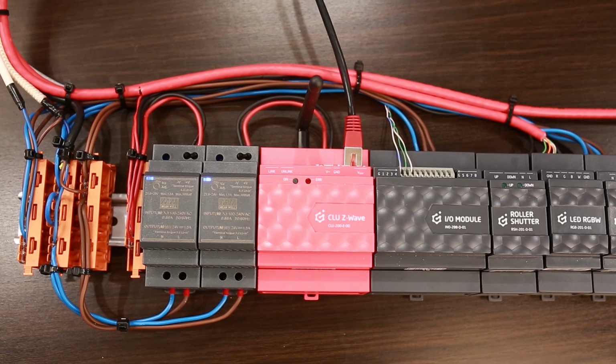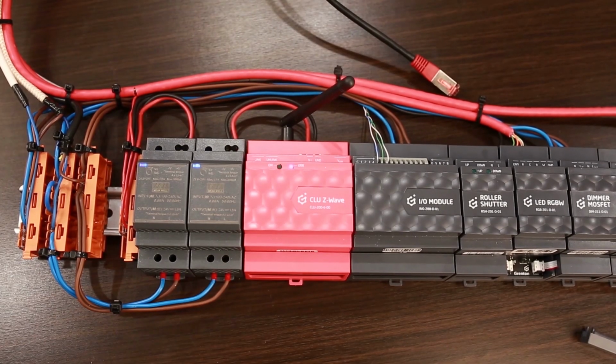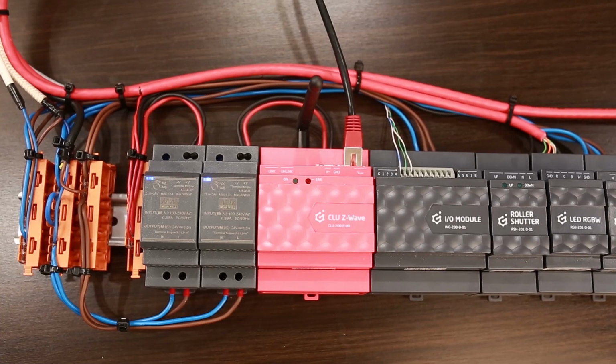This state that was seen earlier, i.e. alternately flashing red and green diode, means the so-called emergency mode, which is typical for a new CLU as it has no configuration yet. If the system has already been configured, it has been programmed, the only valid state is the green LED, which blinks at a frequency of 500 ms, which is exactly how we see it on our CLU module.